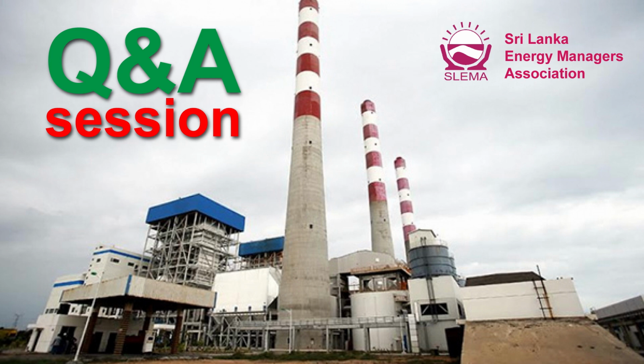Is there any quick response mechanism for reconnection of the grid to at least one of the 300 megawatt units after a blackout? Reconnection is only possible if, after a blackout, you manage to somehow run the cooling water pumps, the boiler feed pumps, the main cooling water pumps in the condenser and all associated auxiliary equipment. Then you can reconnect your unit.